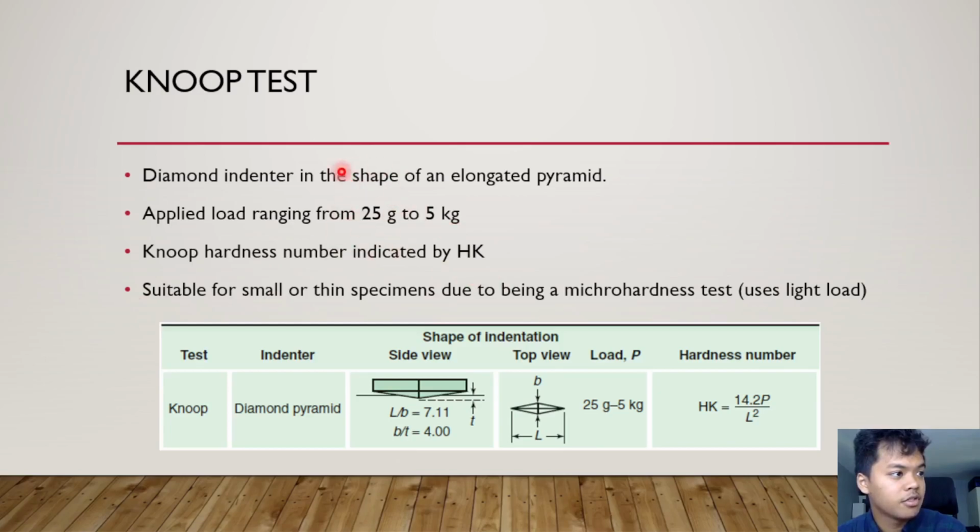So, as I have previously mentioned, ranging from 25 grams to 5 kilograms, suitable for small or thin specimens due to being a micro hardness test, uses light load.